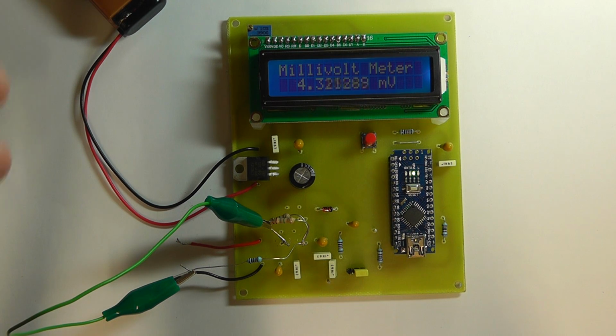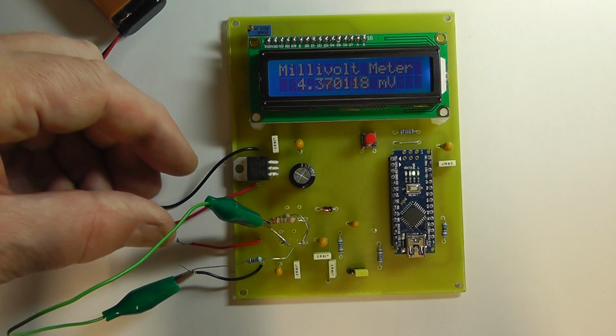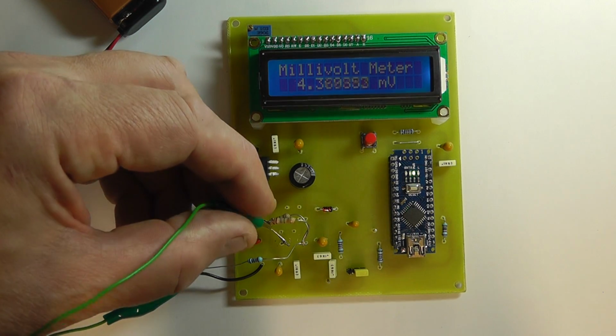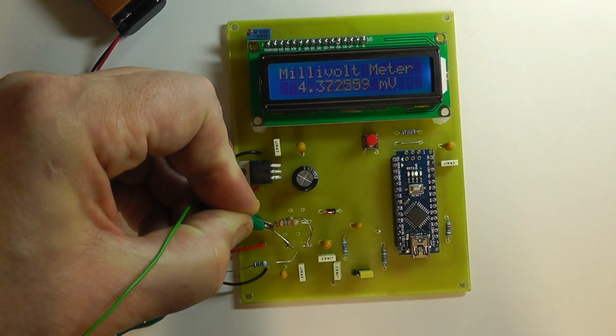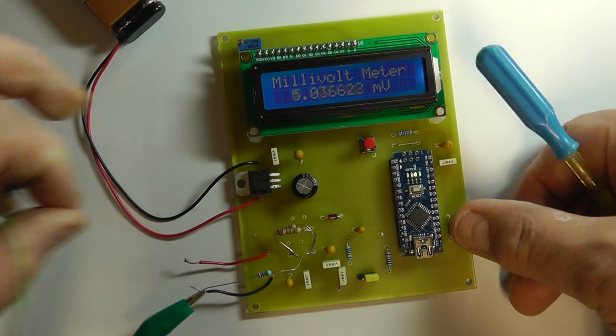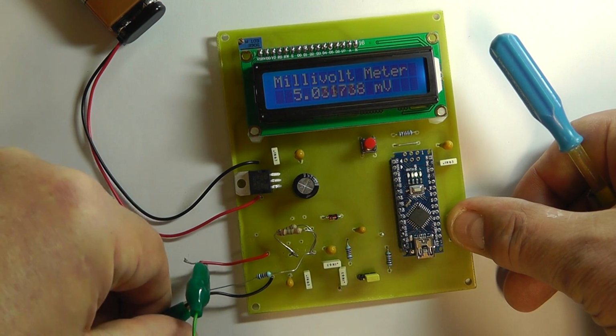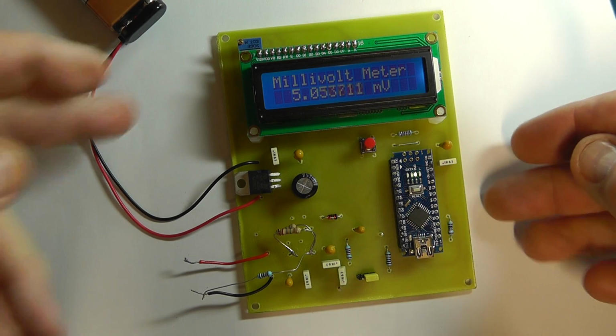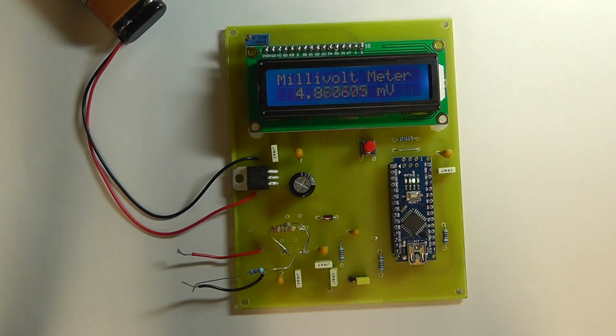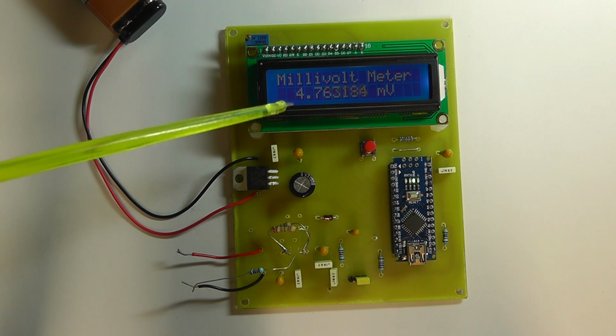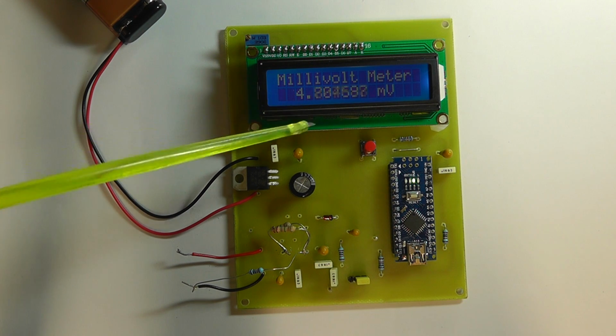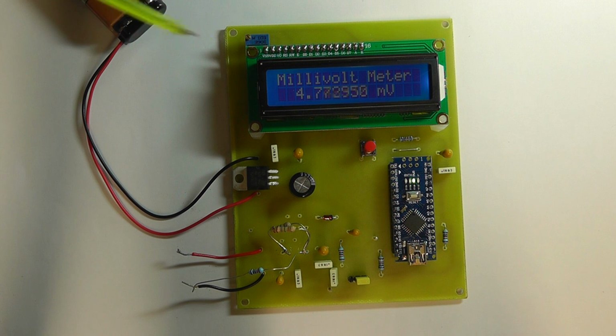We may have to trim the calibration later when we finalise the project, but let's see how it goes for now. If I remove the shorting link on the input, obviously with a meter of this accuracy it's picking up a little noise, showing as a millivolt reading of 4.7 millivolts, going down to 6 decimal places.